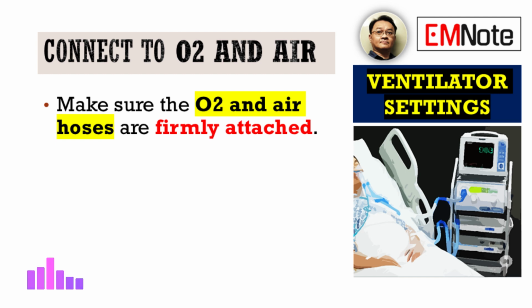So verify the connections are tight, maybe give them a quick pull test, and check that there are no audible gas leaks. None. This final connection point is the direct link between the gas source and the patient's breathing circuit. Its integrity is paramount for continuous, effective gas delivery.